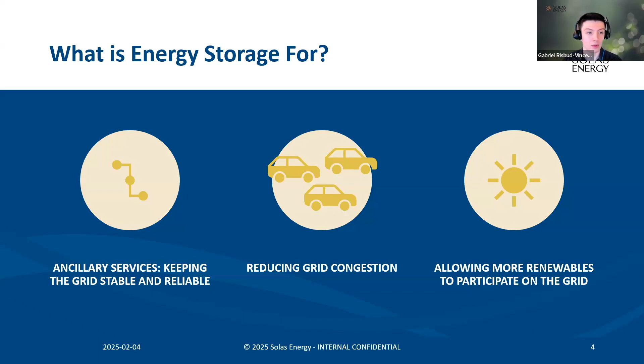Say you have a 200 megawatt hour system that has 200 megawatt hours of energy, and it can output that energy at a rate of 100 megawatts. So you do 200 megawatt hours divided by 100 megawatts, you get a 2-hour duration for that storage system. That falls into the category of short duration, and short duration can include batteries.